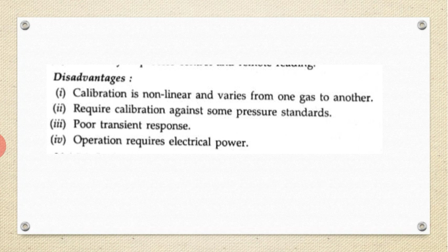The next one is the ionization gauges. These gauges are used for measurement of pressure as low as 0.000001 micron, so one billionth of a mm of Hg. That means you are going to measure very low pressure. The maximum pressure which an ionization gauge can measure is about 1 micron.